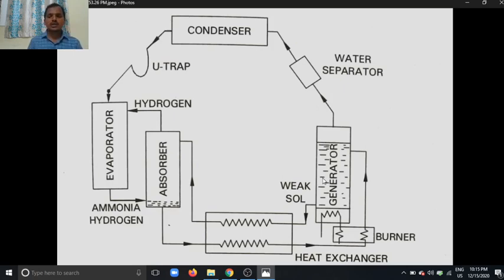The cycle then repeats. The ammonia is separated from the rich mixture, converting it to a lean mixture. The lean mixture goes back to the absorber through the heat exchanger. This motion of the weak and rich mixture is due to the relative positions of the absorber and generator. In this Electrolux refrigeration system there are no moving parts, so there is no noise and no friction, meaning the lifespan is longer compared to the vapor compression refrigeration system. This system is also called a three-fluid refrigeration system.